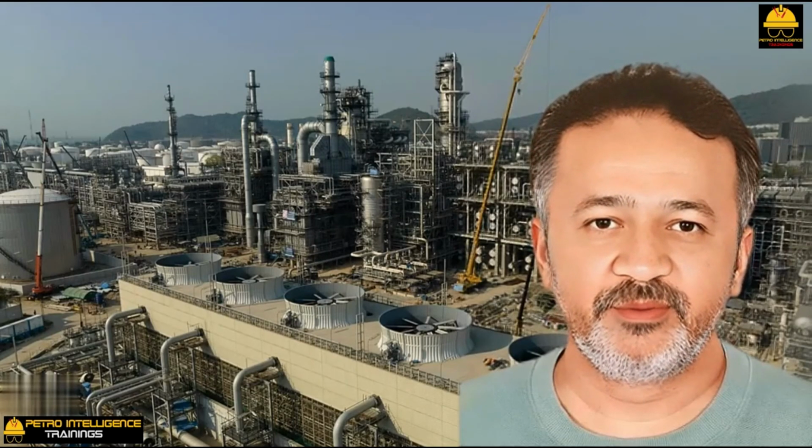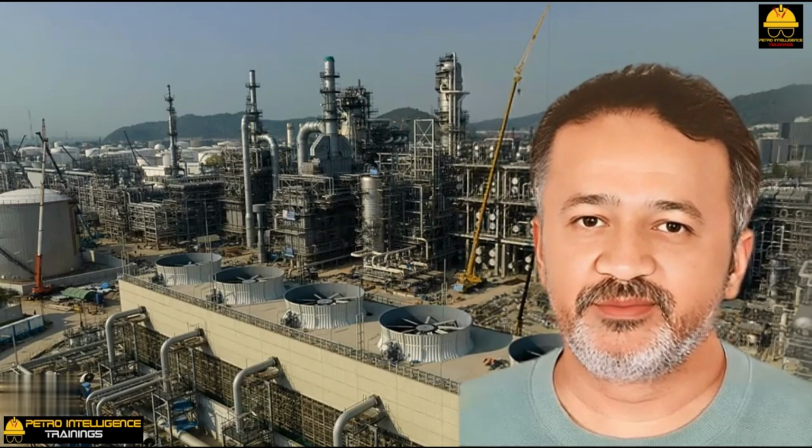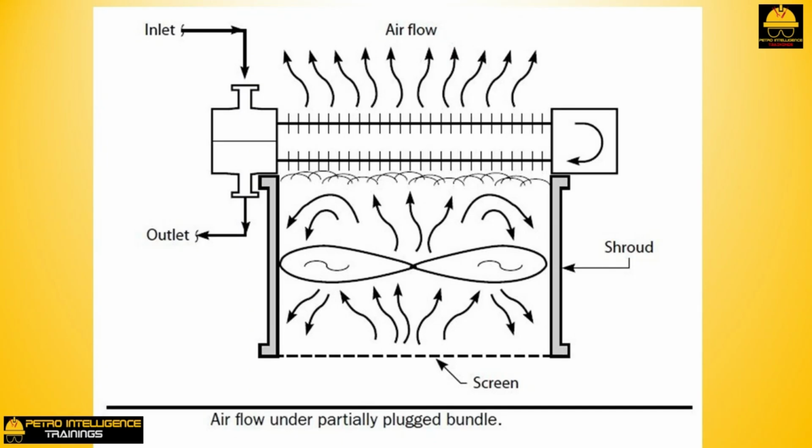Walking across a fin tube bundle will crush these fins. It looks bad but does not appear to affect cooling efficiency. Take a close look at the picture.